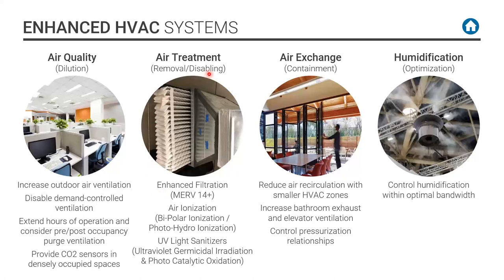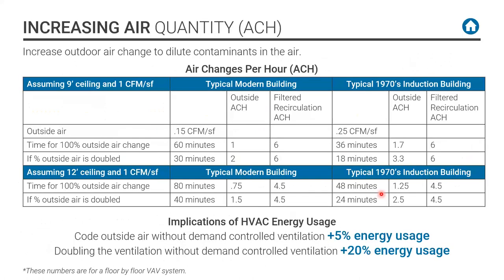And then you can disable contaminants. There's systems that can disable what's in the air, the contaminants in the air, through ionization, which we'll talk about, and UV light sanitation, which is very, very well studied and a proven technology. We'll talk about air exchange, recirculation of zones. The smaller the zone, the less chance of a virus going from one person to another, increasing bathroom exhaust, elevator ventilation, keep air motion in elevators, and of course, pressurization relationships between spaces, especially residential. Humidification can help limit people getting sick and transmission because our immune system is more robust when it's in a 40 to 60% RH situation.